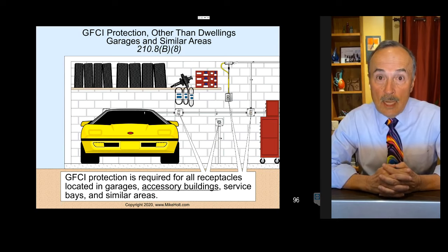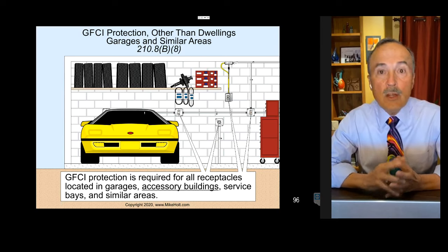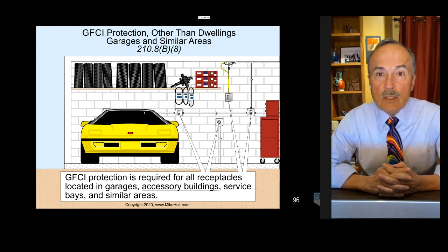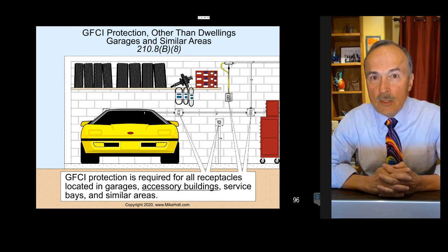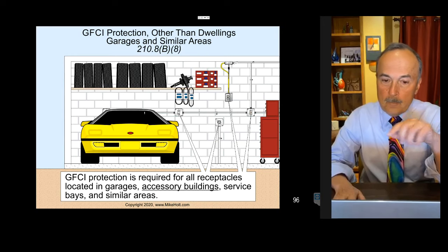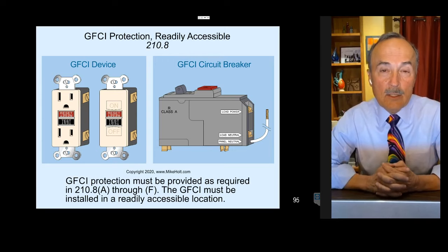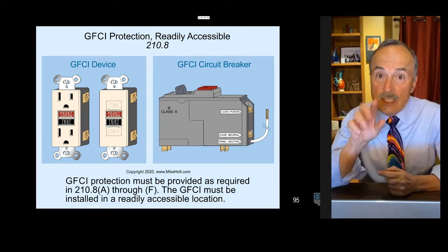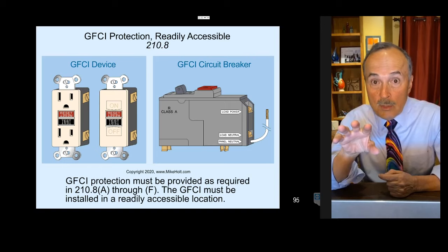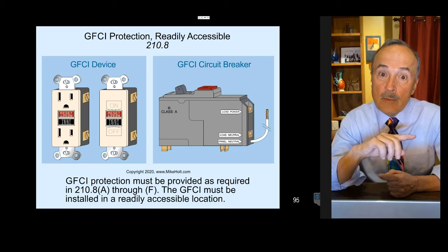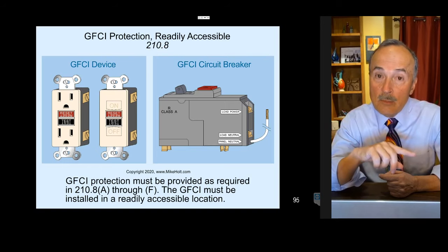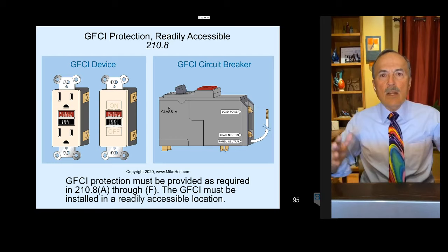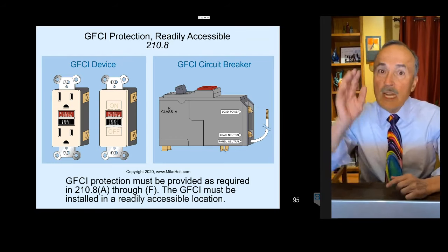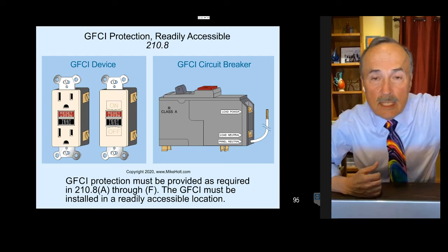210.8(B)(8) says any receptacle in a garage, doesn't matter how high they're located, doesn't matter where they are, but in the 2020 code, any receptacle, that means 240 volt rated receptacles as well as 250 volt rated receptacles as well as 125 volt rated receptacles, have to be GFCI. But 210.8 tells us this. The GFCI test button, effectively what we're talking about, has to be readily accessible.